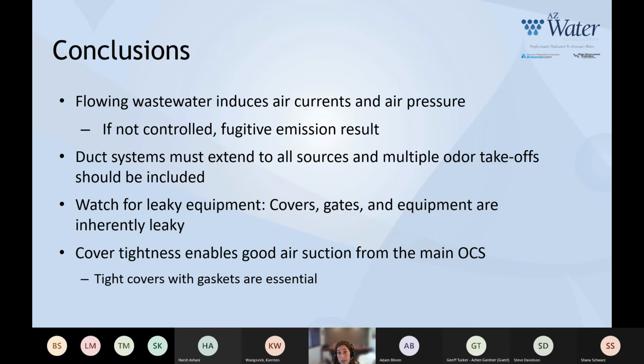Watch for leaky equipment. The covers themselves were inherently leaky. There were gaps between them. So covers, gates, and equipment are all inherently leaking, so look to tighten those up where you can, because it improves your suction draw from the foul air system. Cover tightness enables good air suction from the main odor control system. Tight covers with gaskets, which is what we had recommended, are essential.